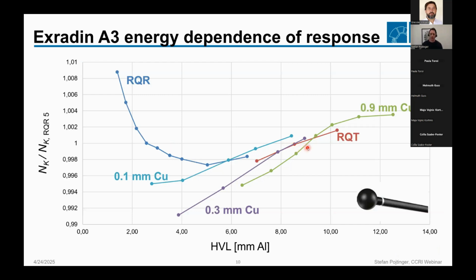If you look at how that plays out for a secondary standard ionization chamber, here I gave an example, an Exradin A3 ionization chamber that is often used. You can see that it makes a lot of sense to introduce these radiation conditions, because here the calibration coefficients of this, so to say, very good detector also change. If you add 0.1 millimeter of copper and look at the same HVL value, you get different calibration coefficients compared, for example, to the standardized RQR radiation series. And if this is clinically relevant, it makes a lot of sense to do calibrations for that kind of filtration.